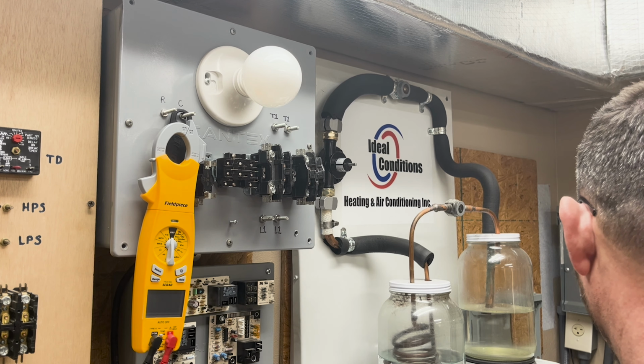If I read across the top side of this contactor, you'll read 0. If I read to the bottom left side of this contactor, you'll read 0. Now watch this - 240 volts.